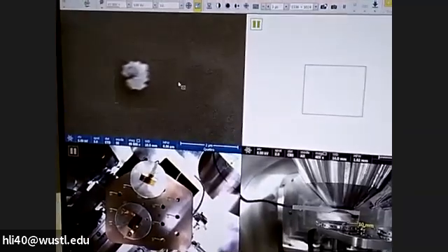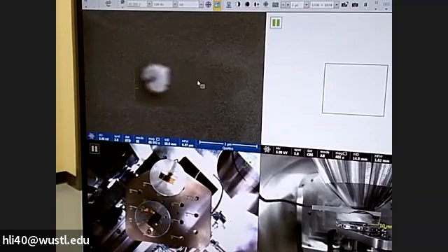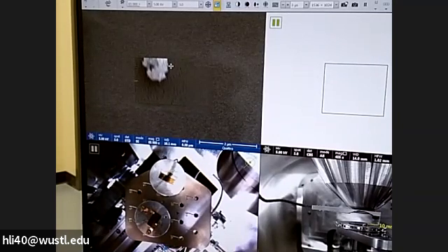If you look at this particle here, you can see when I adjust the focus knob, it becomes blurry and clear. It's pretty much in focus. It's good. And if I turn more, it will become elongated in the vertical direction, right? So let's take it back. This is called astigmatism. So we turn the knob back to bring it to focus. If I turn the knob more, it will elongate in this direction, which is about 90 degrees from the earlier elongation.